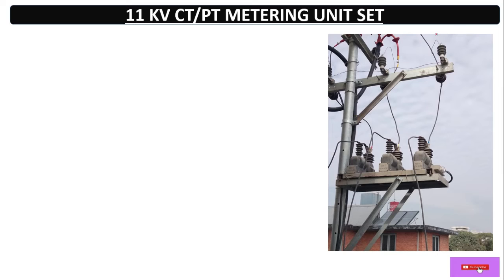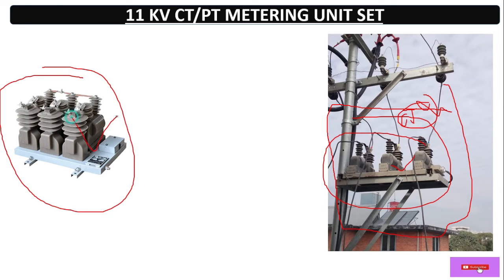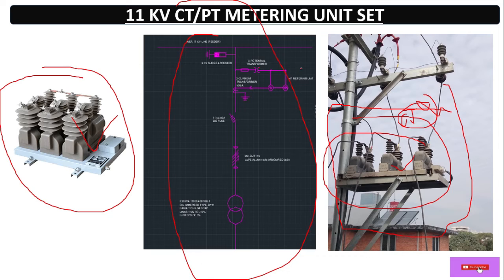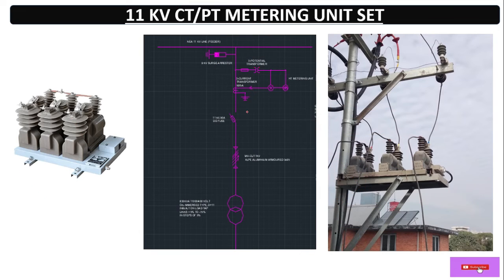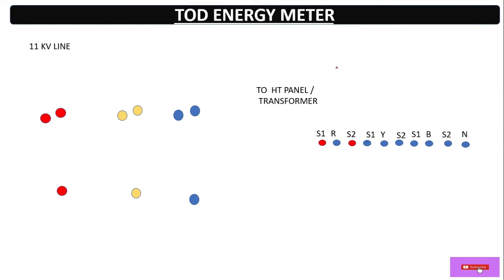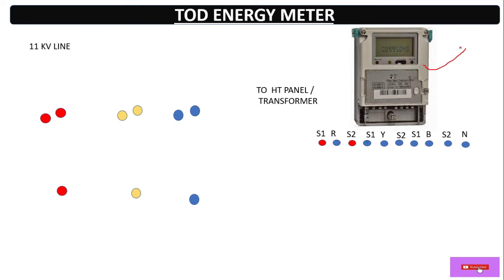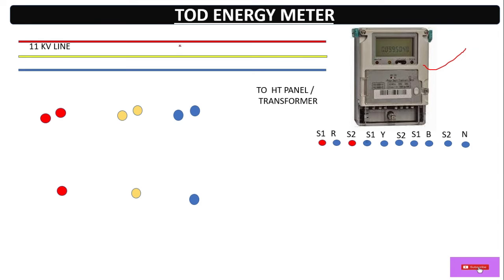Now let's come to the wiring. Here we have a pole-mounted service station where we have a CTPT metering unit. This is a combined CTPT unit mounted on the pole. This is the SLD showing the assembly of the CTPT unit to measure HT side current, voltage, and energy. Let's do the wiring for an 11 kV line. We take the HT meter — also called a TOD energy meter — and here we have an R, Y, B 11 kV line.